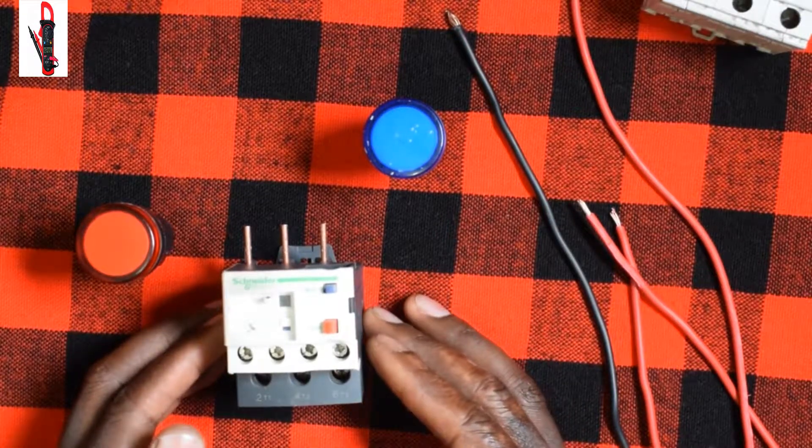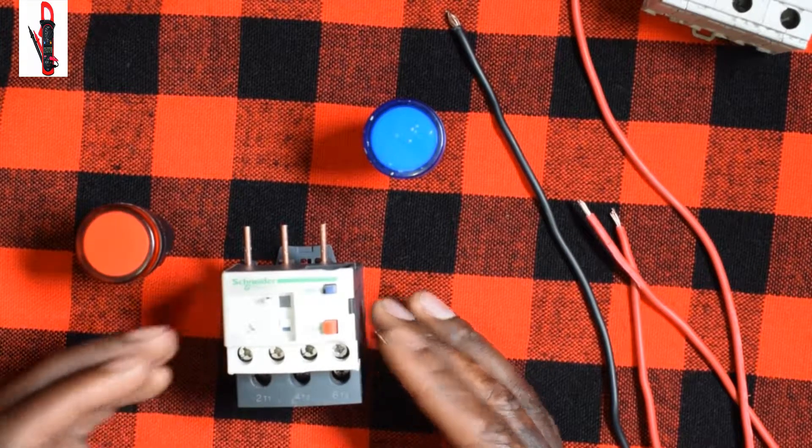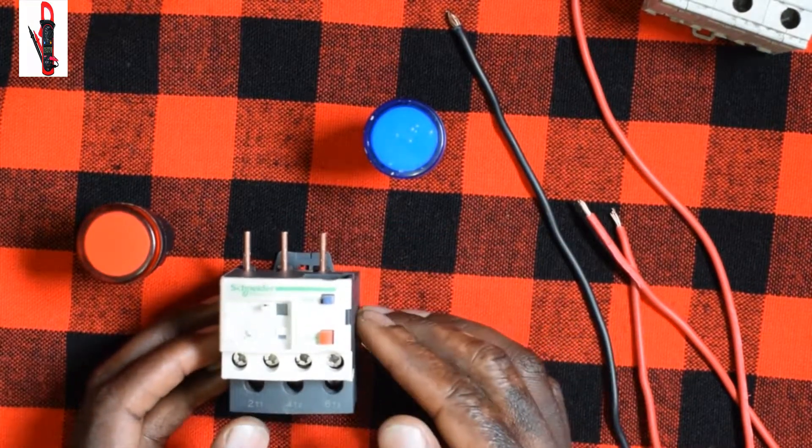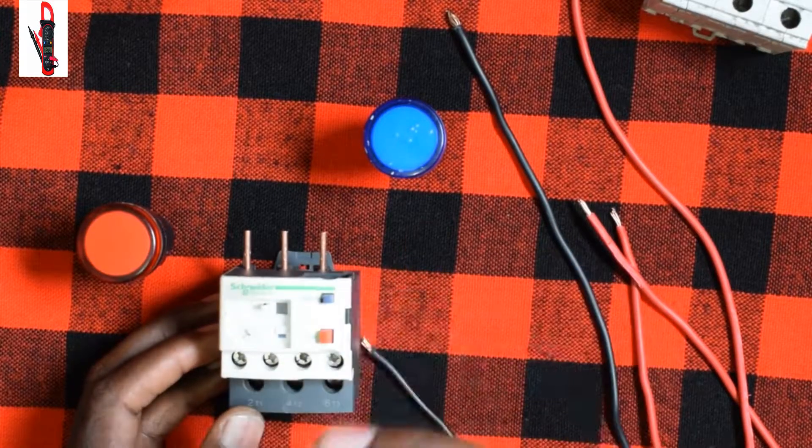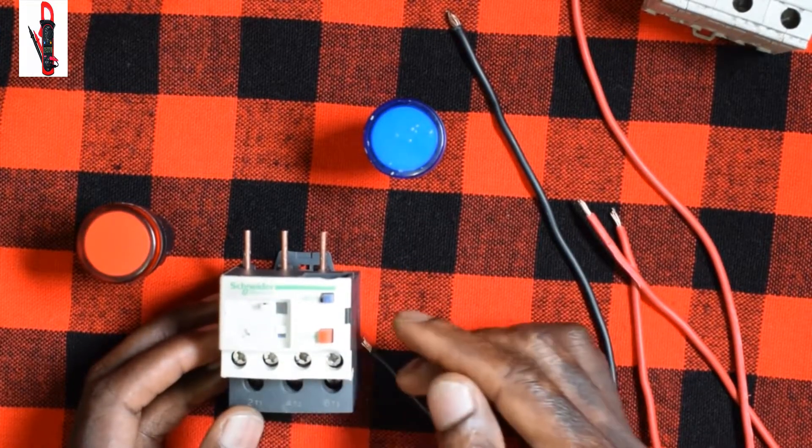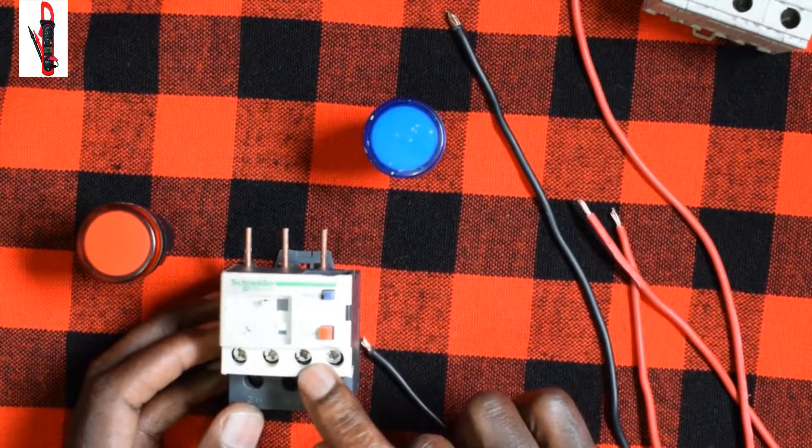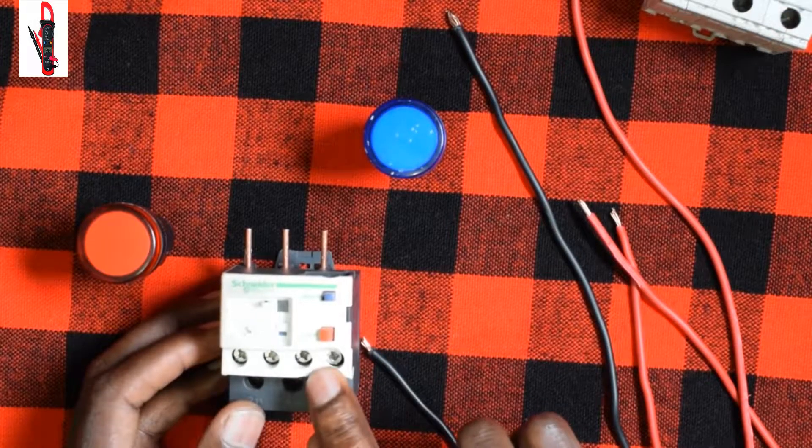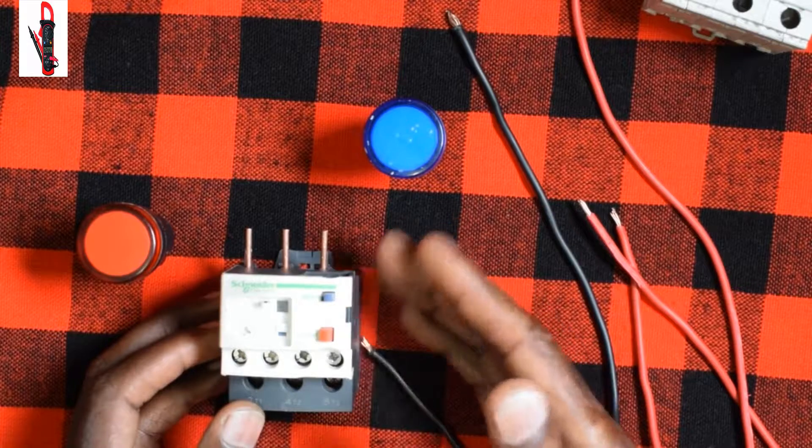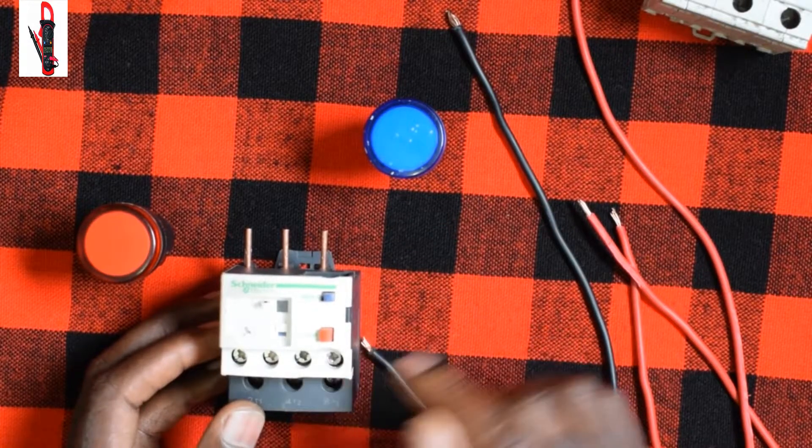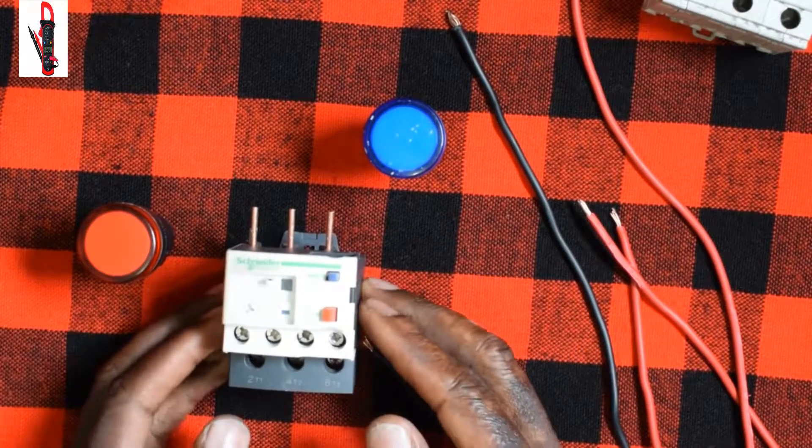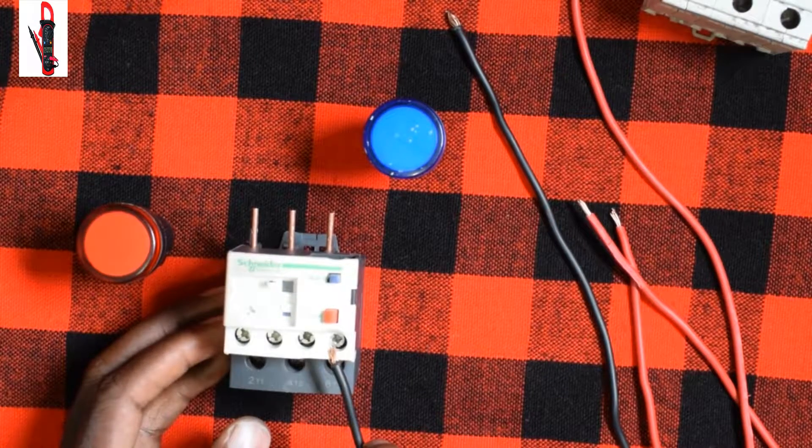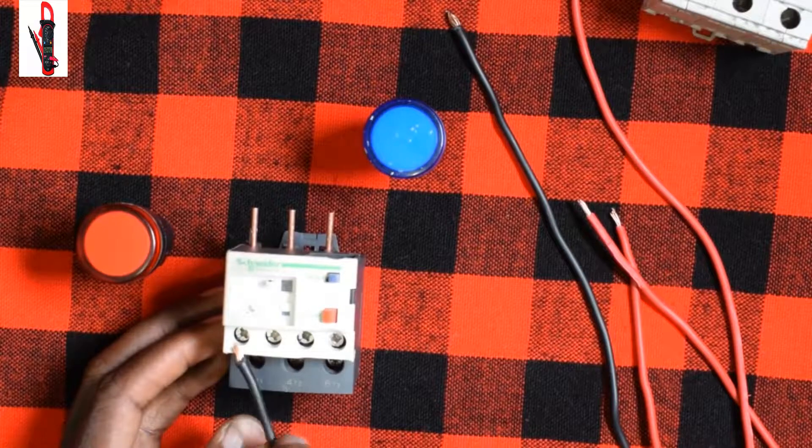If it draws more current than the overload can withstand, what happens is that before the motor burns, if it senses high current it will break. Remember, our control circuit has passed through the 96 and 95 which is normally closed. So the overload will sense that overload current and it will cut the circuit, or you can call it disconnect. It will disconnect the circuit, and that means that the part that is normally closed will now be the vice versa - the other side of normally open will close and this one will open.